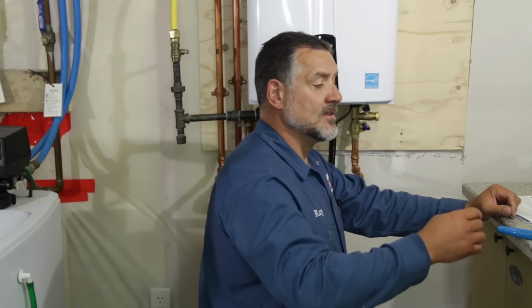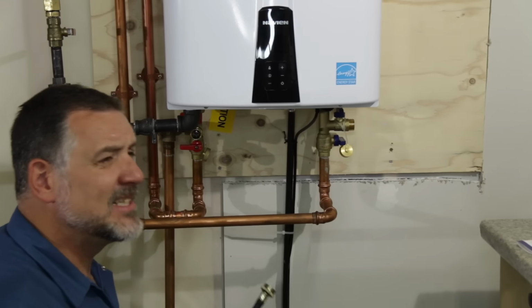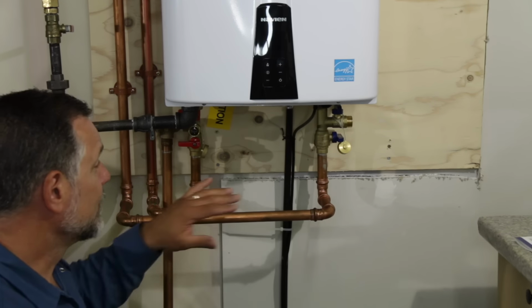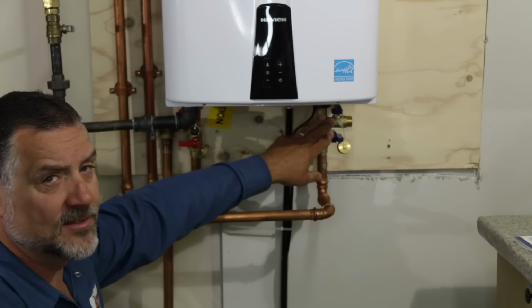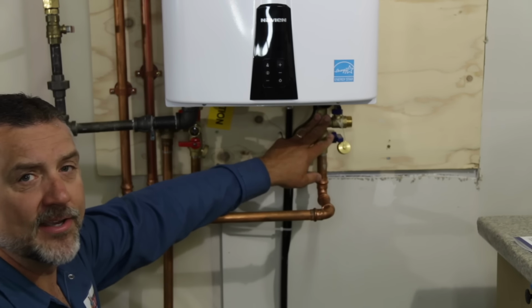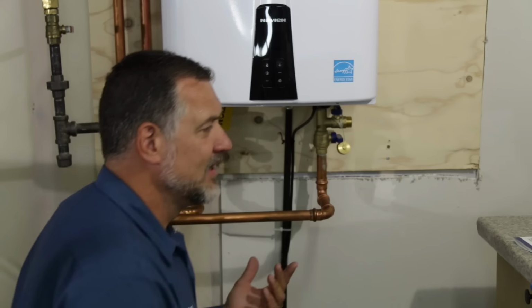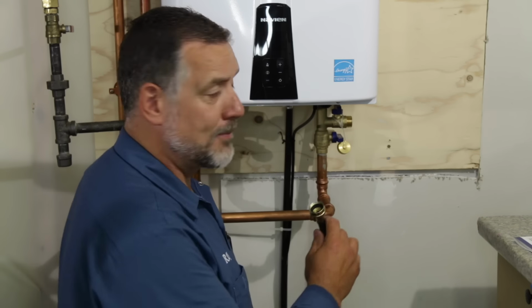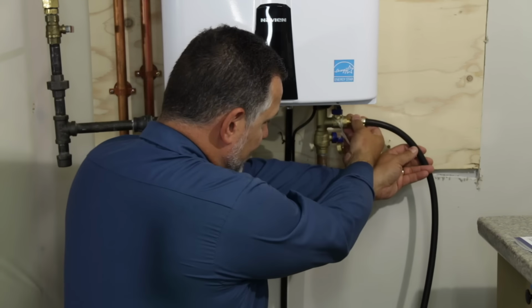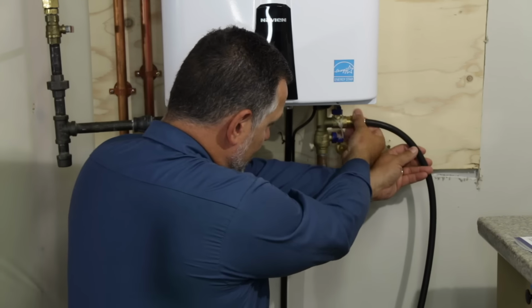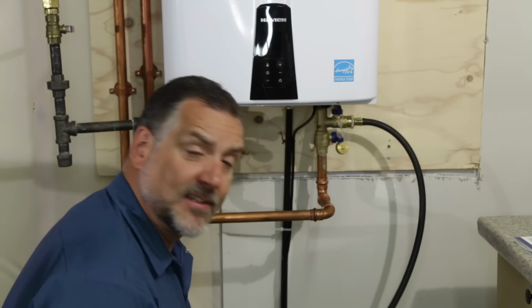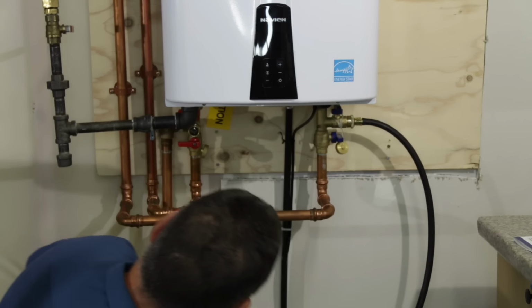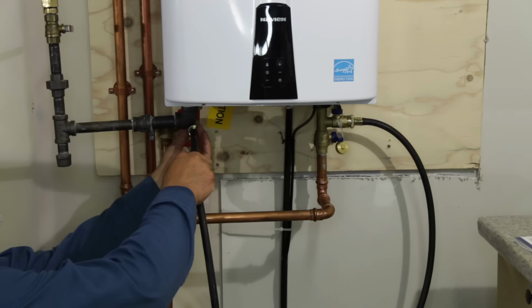You take off the cap on the cold water service port. Every time we install a Navien, it's really important to have these service valves installed. We do that on every single heater, because without that it would be difficult to impossible to clean it properly. So we hook it up to a service valve, and just hand tight is fine. You don't even have to tighten it down with a wrench. And then we'll hook it up to the hot service port.